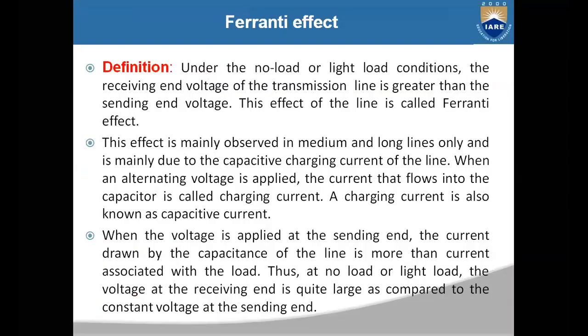Let us first see the Ferranti effect. What is Ferranti effect? Under no load conditions or light load conditions, the receiving end voltage of the transmission line is greater than the sending end voltage. This effect of the line is called the Ferranti effect.